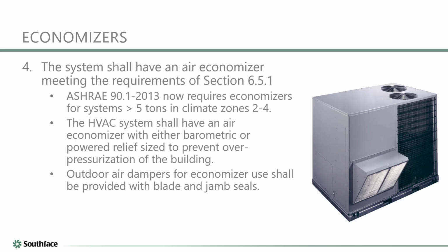and you can take advantage of the nice weather conditions outside by turning off your condensing unit and using your fan to bring outside air into your building and distribute it through your building, and benefit from the fact that you don't have to dehumidify or cool that air because it is at essentially the conditions you are looking for. And that's what an economizer does. As you can imagine, an economizer probably doesn't get used nearly as much in, let's say, Valdosta, Georgia, for example, right?